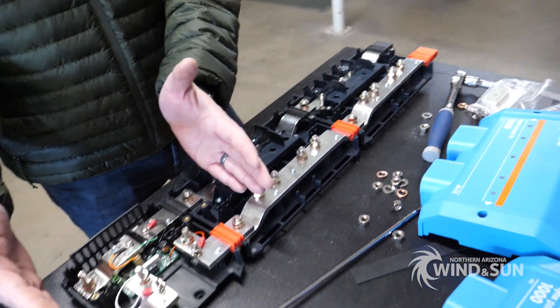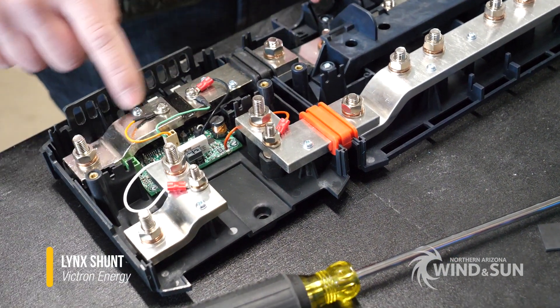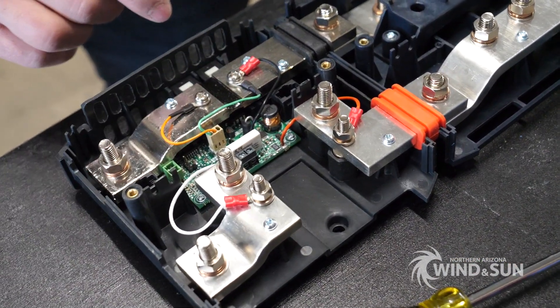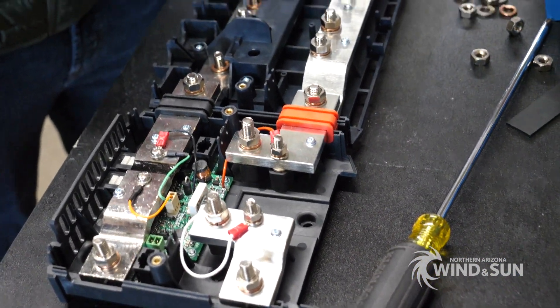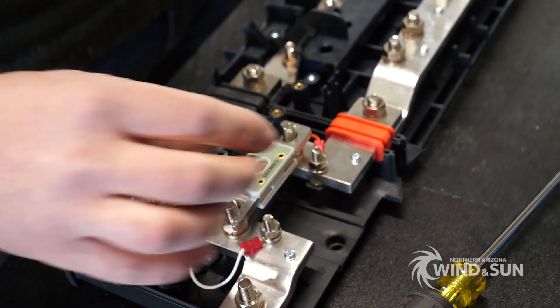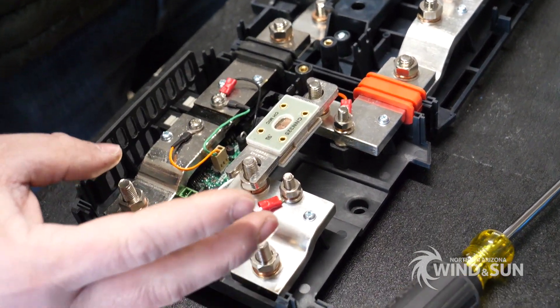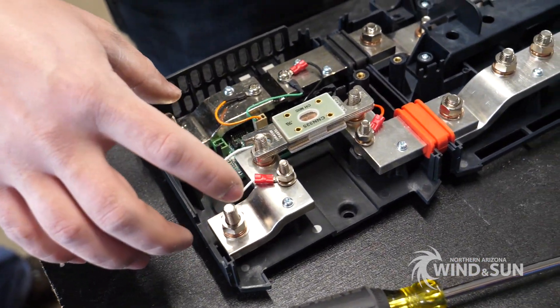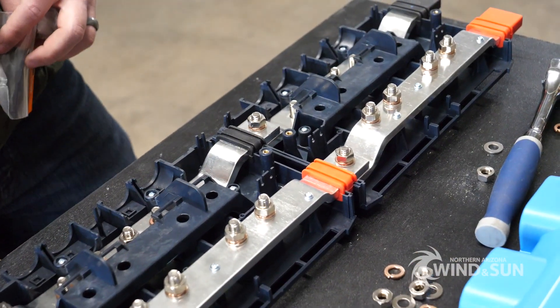This here is the shunt — the Lynx shunt system. It's measuring current down here on the bottom section; this is the actual shunt and the circuit board that monitors the current. This section up here is where the overcurrent protection goes. This is a ANL fuse, and for this project we're going to use a 325 amp ANL fuse, which is essentially going to bolt in here. Our loads will connect onto these terminals here — for example, the inverter, the charge controller, and the rest of the equipment pulling DC loads off the batteries connected over here, to supply power to the rest of the system.